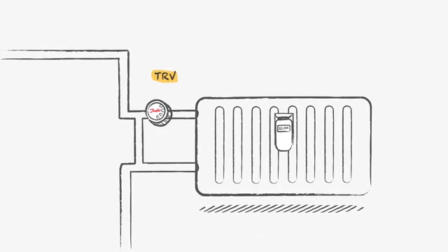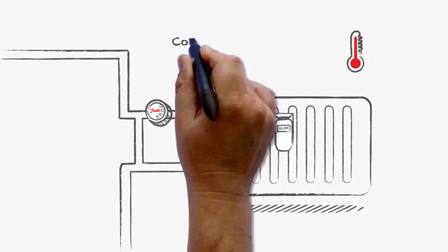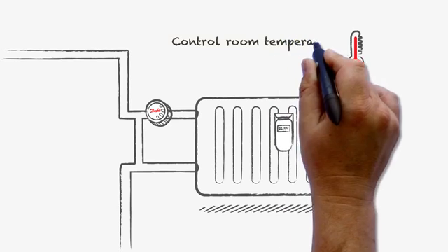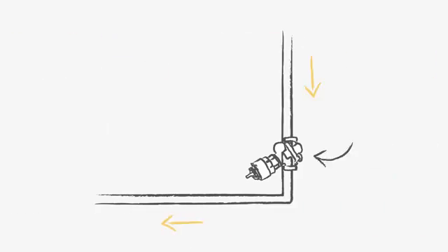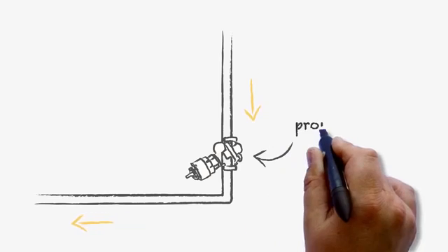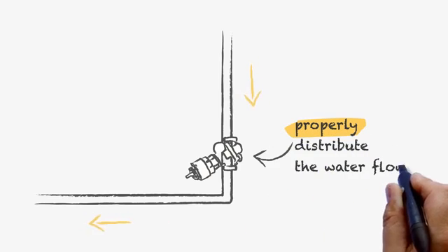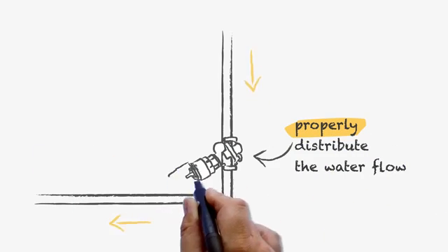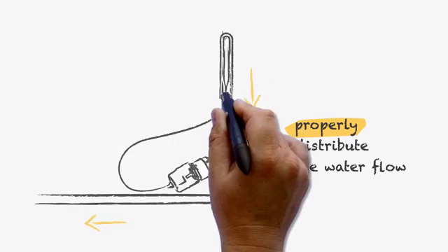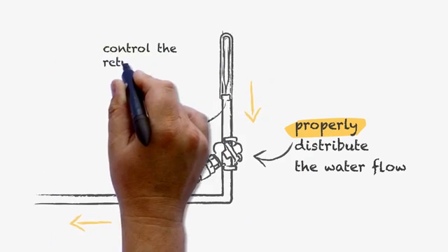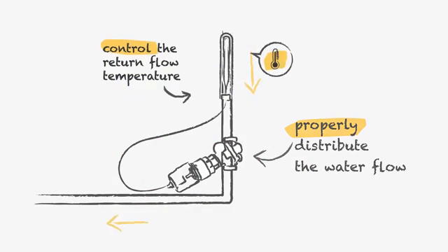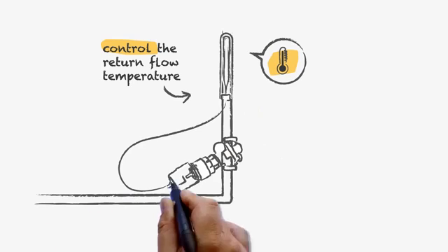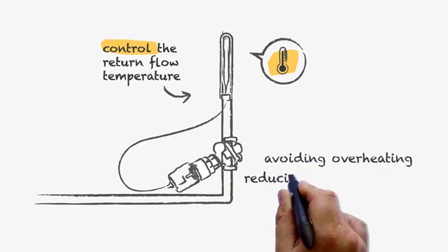The thermostatic radiator valve is there for the resident to control the room temperature. The ABQM pressure-independent balancing valve will properly distribute the water flow through the installation and the actuator with thermostatic element will control the return flow temperature in the riser, avoiding overheating and reducing unnecessary flows.